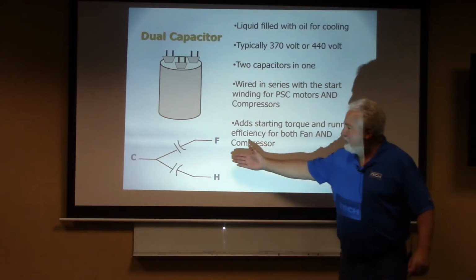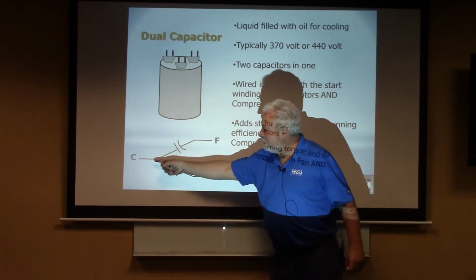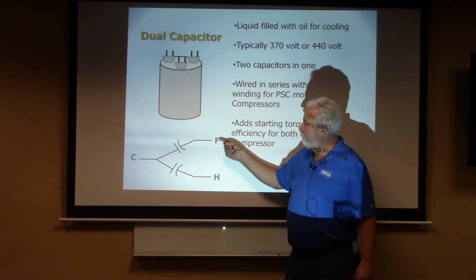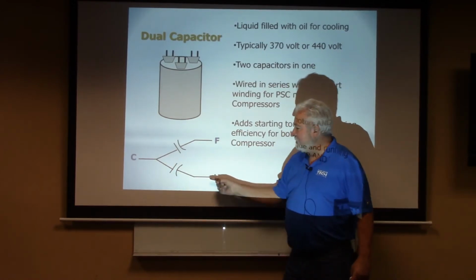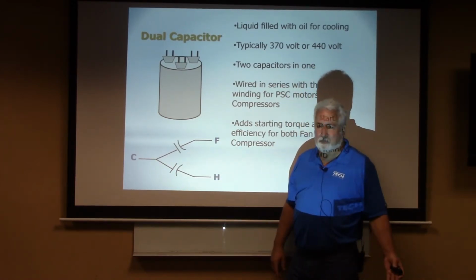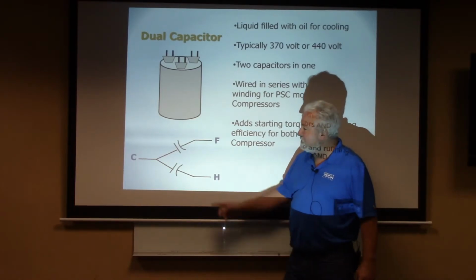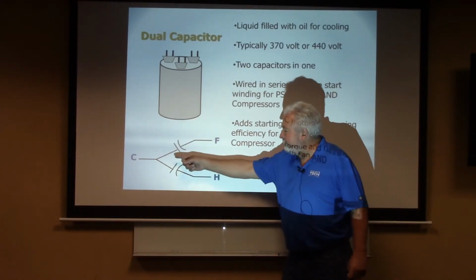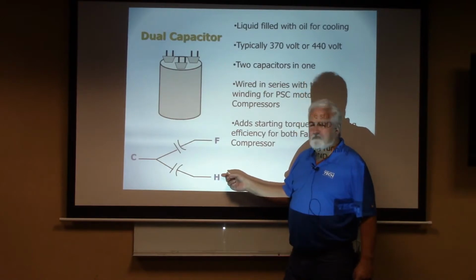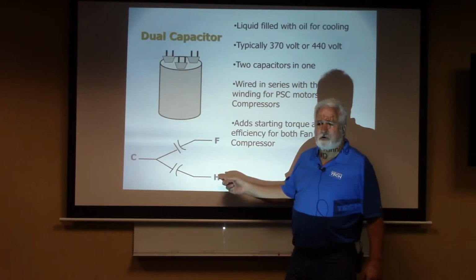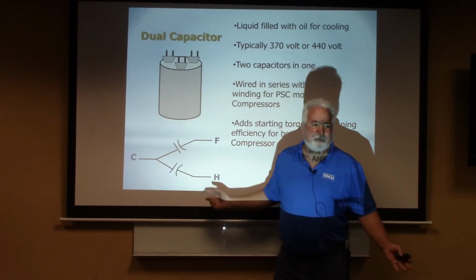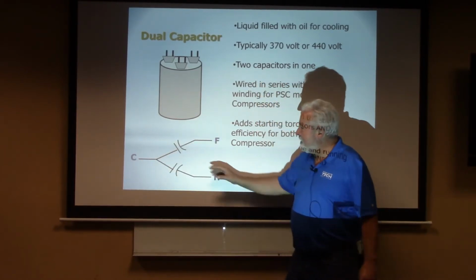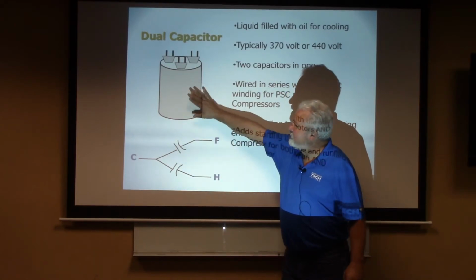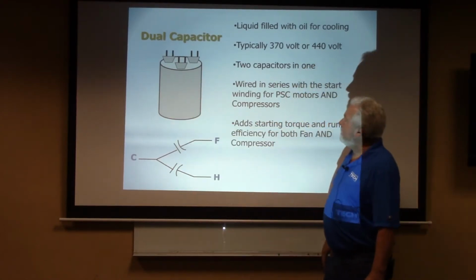So dual capacitors. Dual capacitor. Here's how it's wired. You have a common, comes in here. And then your F is for your fan, and the H is for hermetic, which is compressor, right? It's a hermetic compressor. Why don't they put compressor here? C. Oh, because we used the common already for that one, so we couldn't put compressor. We had to put hermetic. So it's common, fan, common, hermetic.